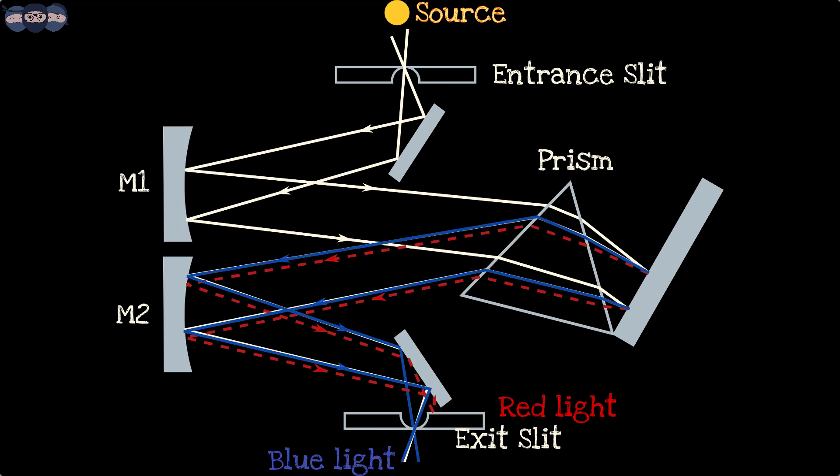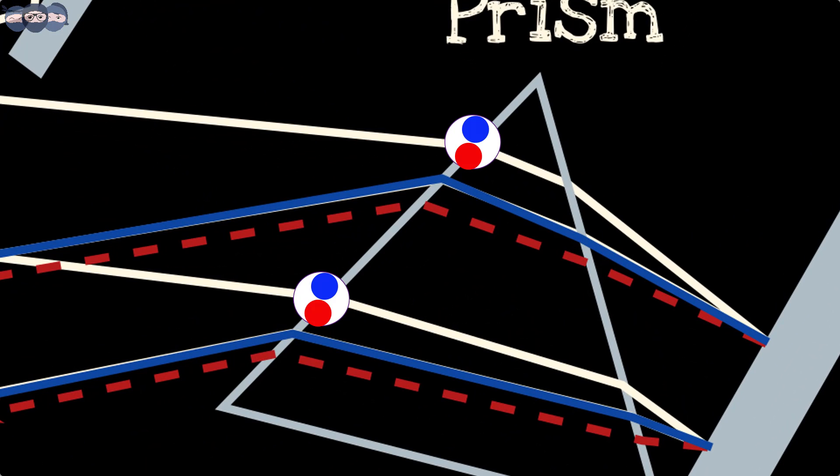Looking at prism monochromator, we can understand its working. Light from the source enters the monochromator through the input slit. This light is focused on a collimating mirror which renders the light beam parallel. This light is composed of different wavelengths.